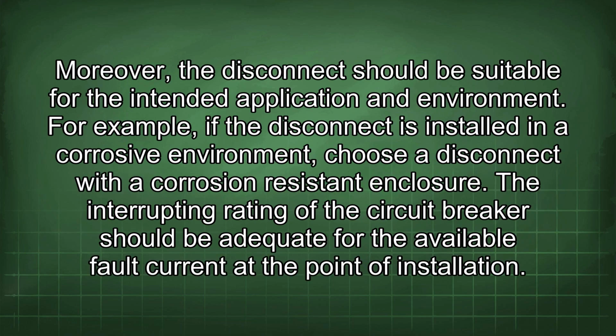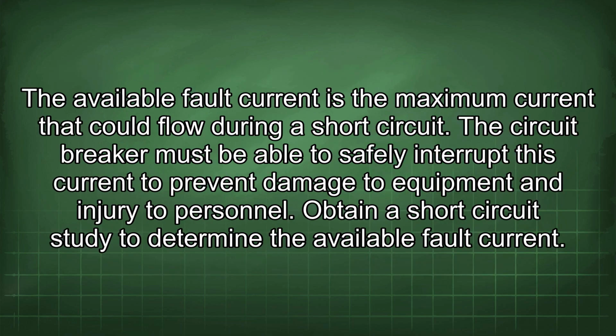Moreover, the disconnect should be suitable for the intended application and environment. For example, if the disconnect is installed in a corrosive environment, choose a disconnect with a corrosion-resistant enclosure. The interrupting rating of the circuit breaker should be adequate for the available fault current at the point of installation. The available fault current is the maximum current that could flow during a short circuit. The circuit breaker must be able to safely interrupt this current to prevent damage to equipment and injury to personnel. Obtain a short circuit study to determine the available fault current.